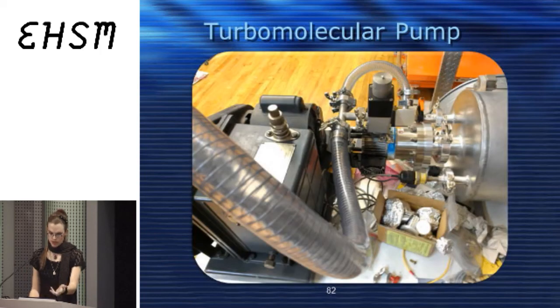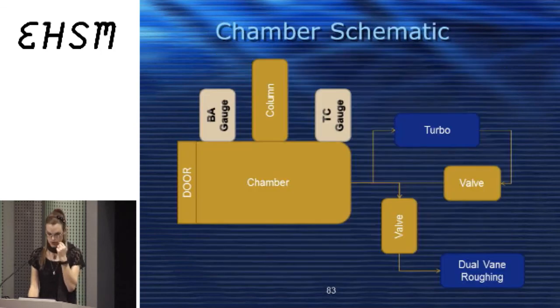There's the turbo pump, some valves, the dual vane rotary. Here's a chamber schematic because honestly it's difficult to see from a photo. So the chamber has a large door. There's a Bayard-Alpert gauge to measure high vacuum. There's the TC gauge to measure low vacuum. The beam column sits, I'll show it in the next picture, on top of the chamber. Turbo pump, roughing valves, roughing pump. It's a pretty simple, straightforward schematic of the vacuum system.